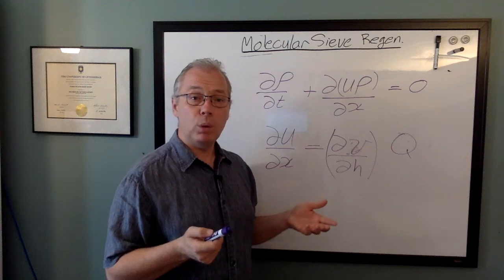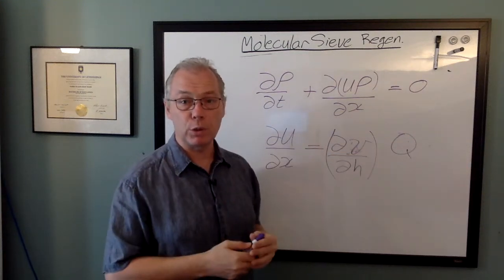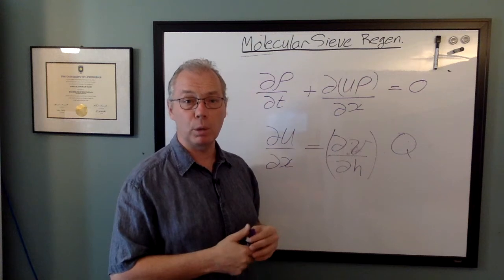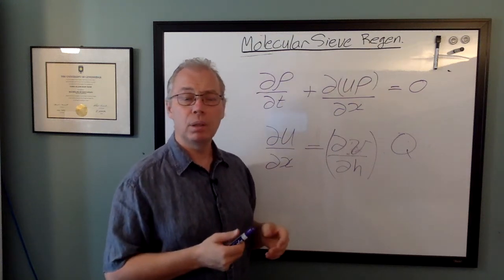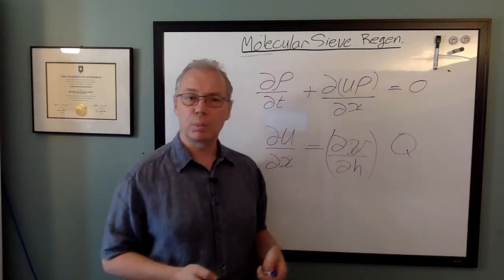The sieve bed holds 8.4 cubic meters of liquid propane, and it's about 1.4 meters in diameter and 6.1 meters high, with a 25 millimeter wall thickness. And it holds 4.5 tons of molecular sieve. Let's take a look at some results.